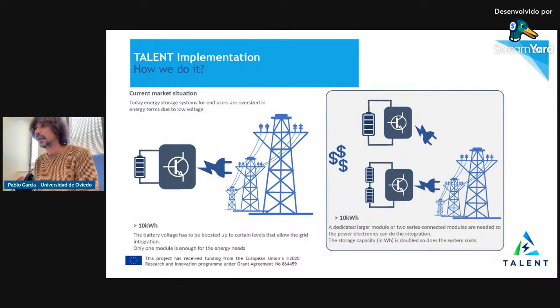And basically, when you want to scale that system in voltage, the problem is that the energy storage modules typically used for these applications have a voltage of typically 48 or 51 volts, depending on the number of cells - 15 or 16 connected in series. When you want to connect that to the grid through an inverter, for that size of energy, considering 1C or 0.5C, the power is going to be in that range.